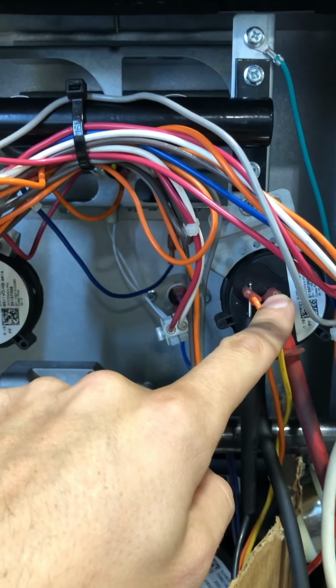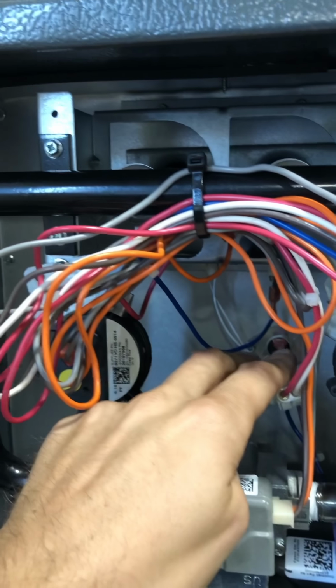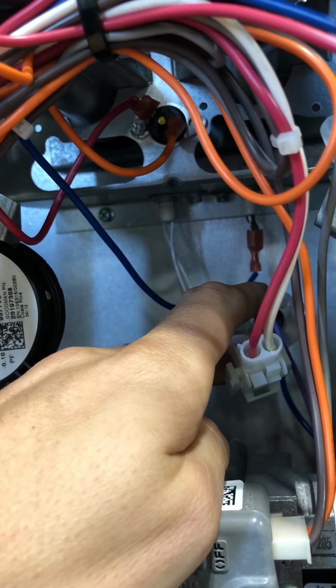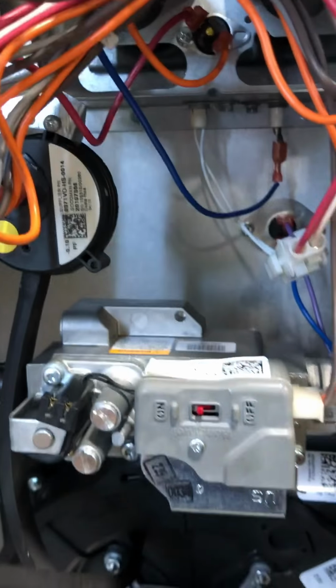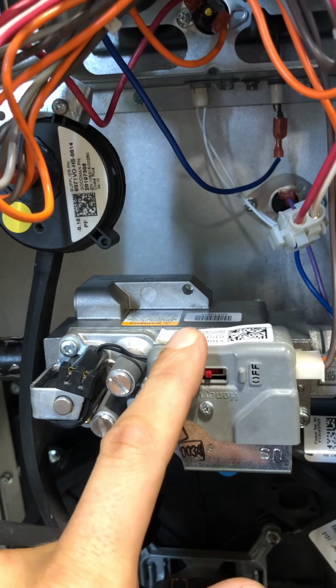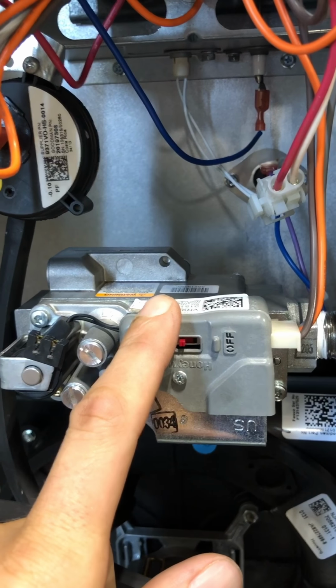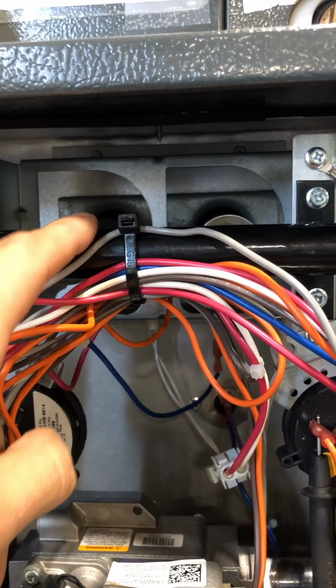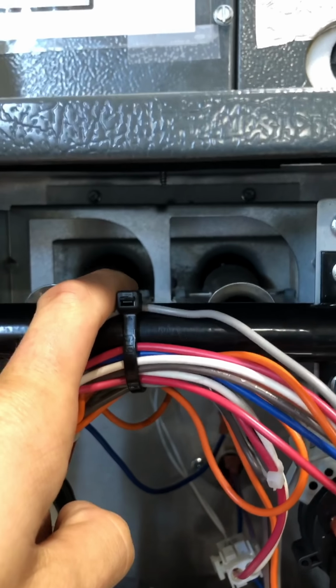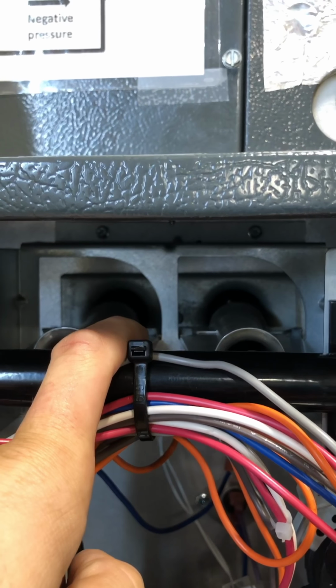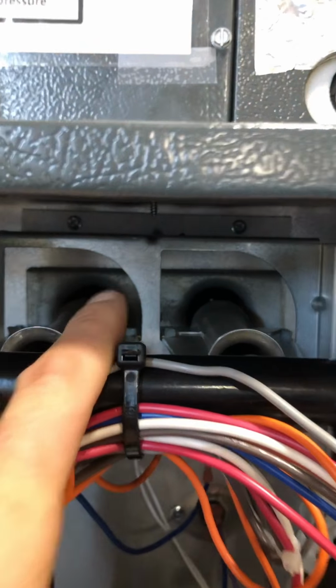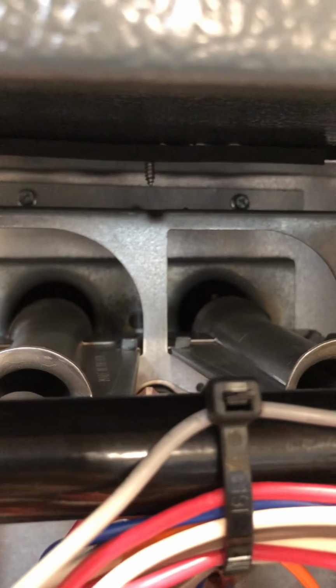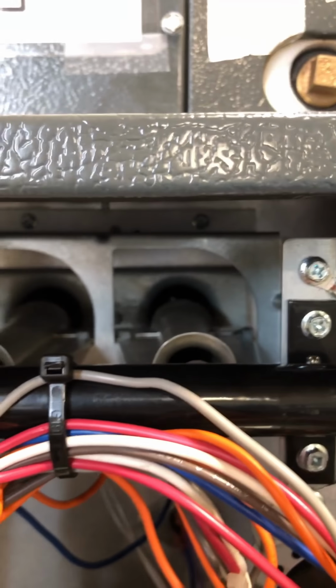After this has come on and we have verified this is closed, after a small time delay, we'll get hot surface ignition. We'll let that heat up for a few seconds. Next, we'll get 24 volts to the gas valve, which will allow gas into the burners, and we should ignite the flame as long as that hot surface igniter is burning hot enough. As soon as we ignite the flame, our flame sensor that's back in there will sense that the flame is actually burning.